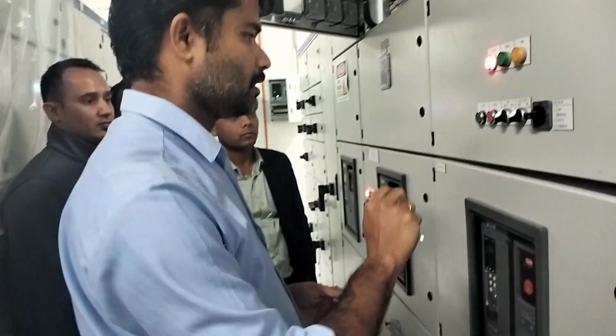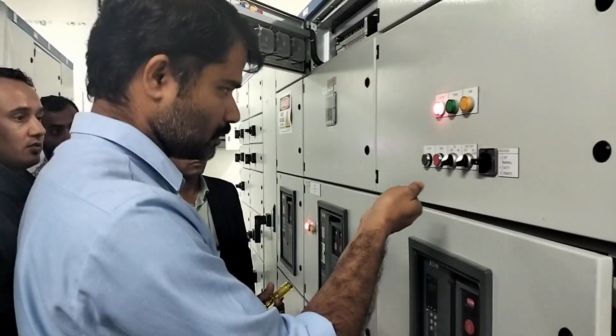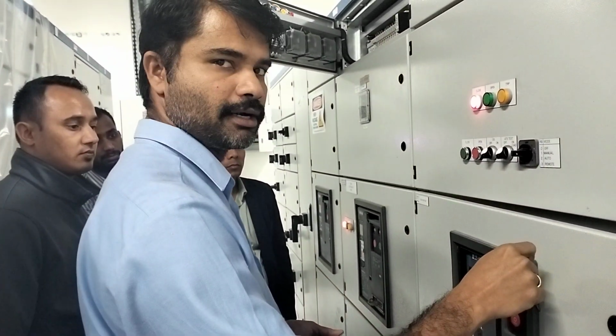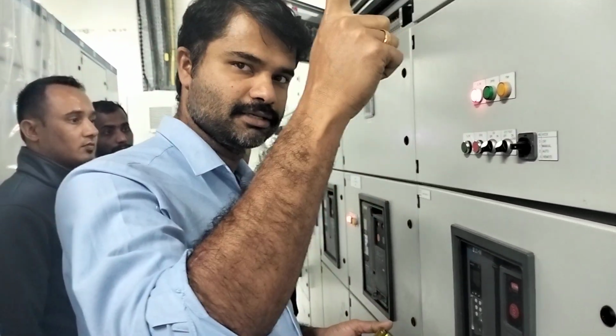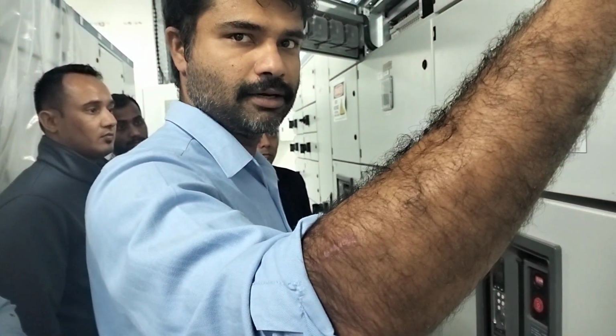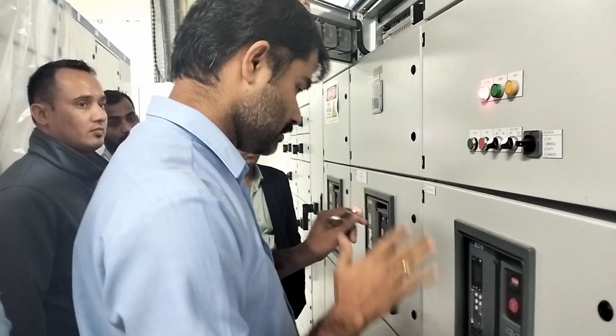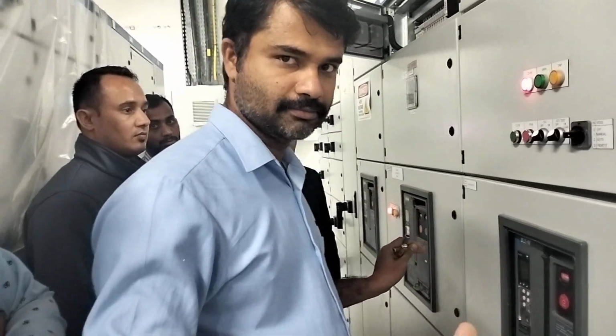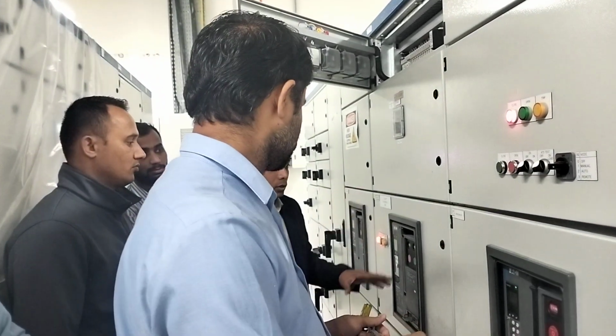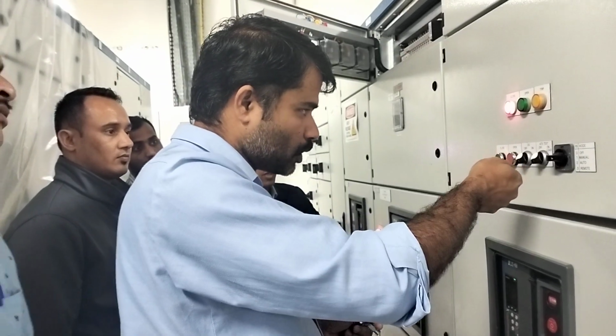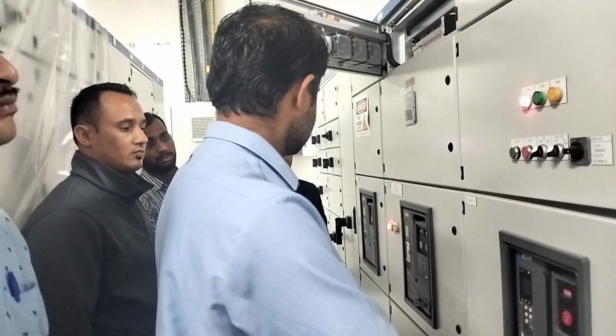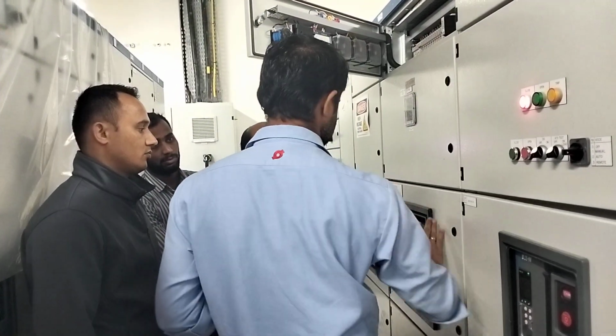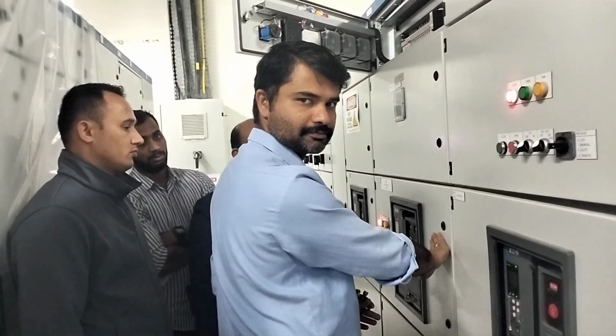This is the auto test. If you want to check the generator, put it in test. What will happen? The coupler will open, the generator will start, and it will close the breakers. But in this condition there is no mains failure, because the power is also there. When you put on load, the coupler will open. This is already feeding the power because the mains is still there. It's the same situation as before in manual. If you put manual, the power is there.